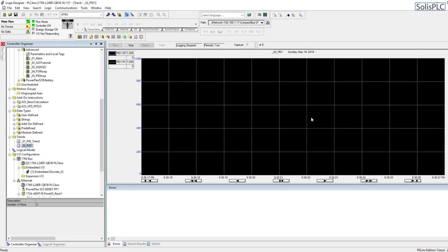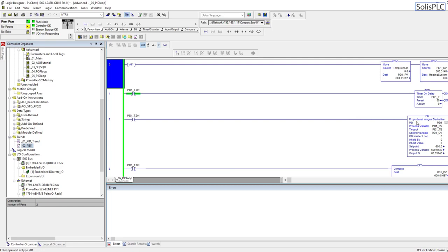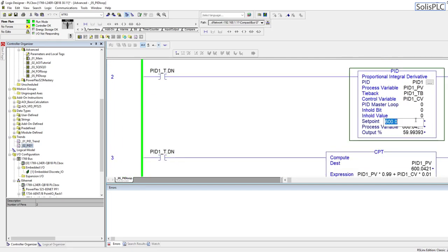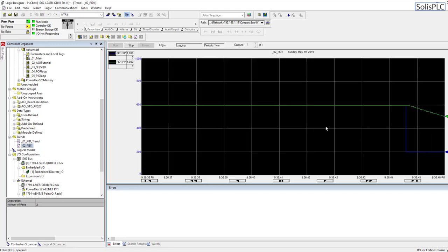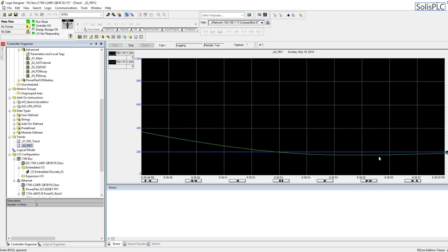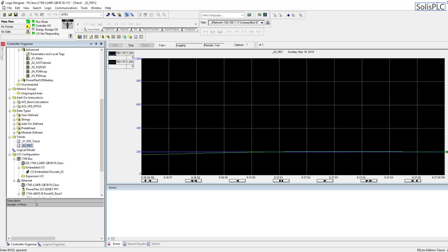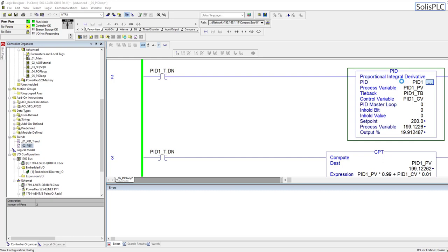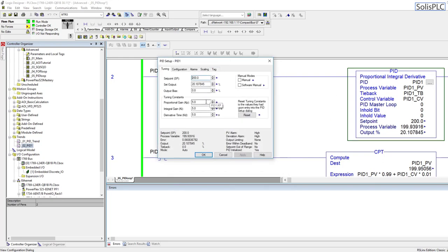The PID loop is definitely running — both values are at 600. Changing to 200, you notice the PID loop immediately starts to react and trend towards the set point, which is exactly the expected behavior. It undershot below the set point, slightly oscillated, then came back — the normal behavior of the loop. Once set up, you can start playing with proportional, integral, and derivative gains, which will highly depend on your application.